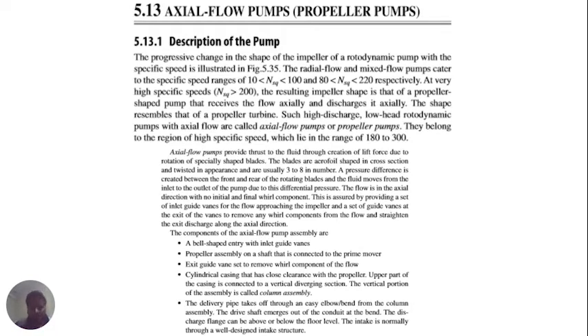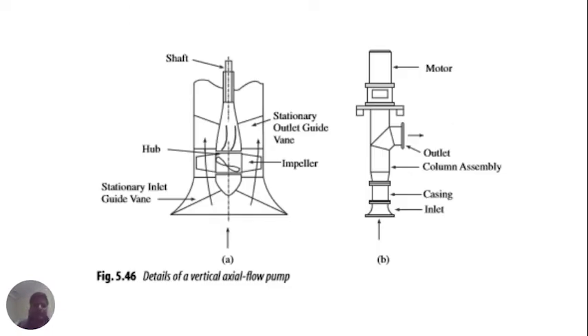Components of the axial flow pump assembly include: a bell-shaped entry with inlet guide vanes, a propeller assembly on the shaft connected to the prime mover, exit guide vanes to remove any whirl component from the flow, a cylindrical casing with close clearance with the propeller, an upper part connected to a vertical diverging section — the vertical portion called the column assembly — and a delivery pipe taking off through an elbow bend from the column assembly. The drive shaft emerges out of the conduit at the bend and the intake is normally through a well-designed intake structure.